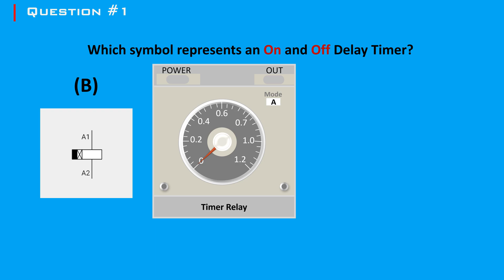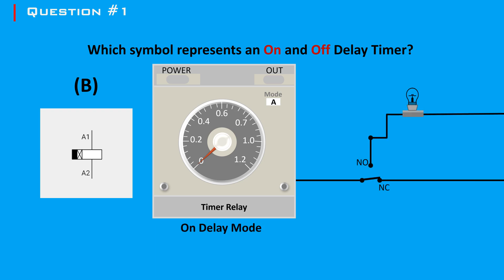Here is how it works, starting with on-delay mode. When the input signal is applied, the timer starts counting the preset delay time — for example, 3 seconds. After the delay time elapses, the output contacts change state from a normally open contact to closed. The output remains in this state as long as the input signal is present. When the input signal is removed or reset, the output contacts return to their original state immediately. This can be used in delaying the start of a conveyor belt to allow other machinery to get ready.